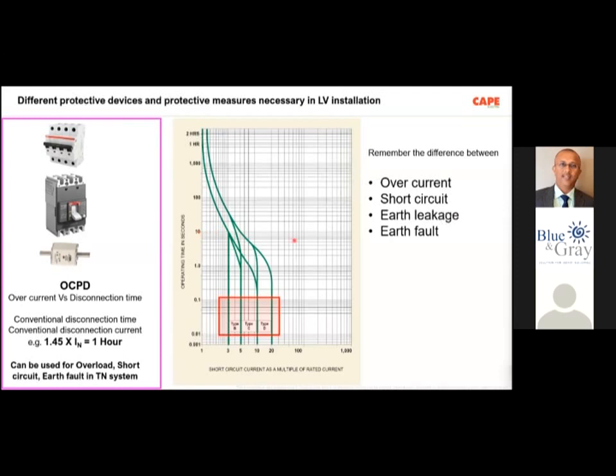Now, to select it, first you should understand the difference between overcurrent, short circuit, earth leakage, and earth fault. If you don't understand the difference between these four, then of course you cannot handle it properly. Earth leakage and earth fault: a fault, when we call it a fault, always means an earth fault. A live conductor is in touch with a metallic object which is not a current carrying conductor.